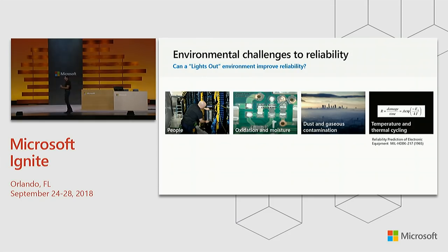The reason why we think this can potentially be interesting is that this is a lights out operation. Besides the obvious thing that it's cooled by the ocean water, and it's liquid cooled, we have liquid water from the ocean coming in, cooling the servers, and we're not touching the servers. It's a lights-out operation. And the theory is, if we don't touch the servers, if humans aren't manipulating them, if the temperature remains constant, if the water vapor is extracted from the air, and the air is extracted from the cylinder, so it's basically a vacuum, and it's isolated from the outside world, that those servers will last longer.